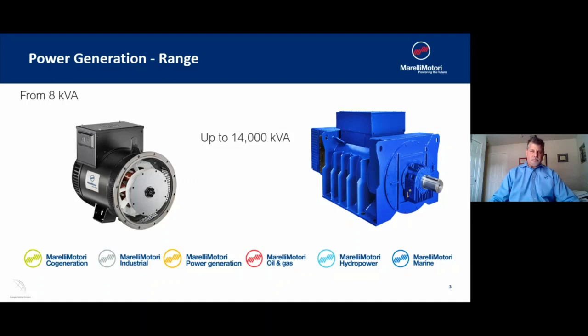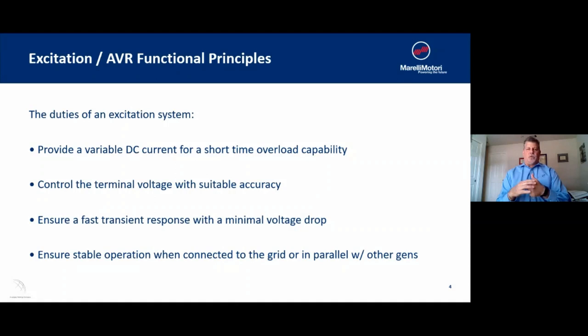Let's get into the functional principles of an AVR — it's fourfold. The duties of the excitation system are to provide a variable DC current for short-time overload, control the terminal voltage with suitable accuracy, ensure a fast transient response with minimal voltage drop, and ensure stable operation when the generator is connected to the utility or in parallel with other generators.